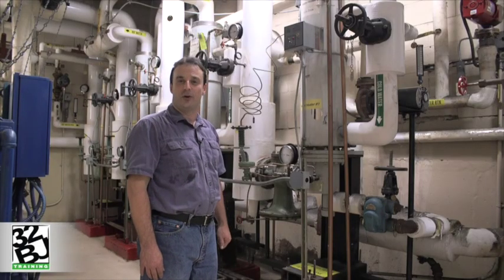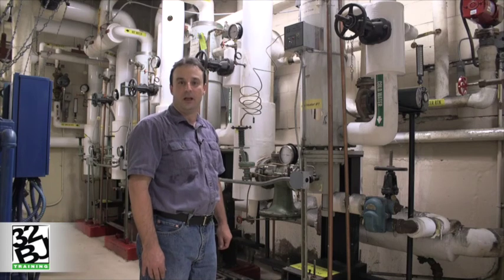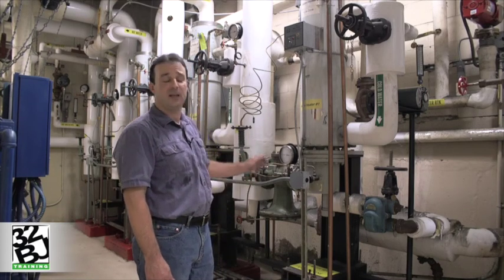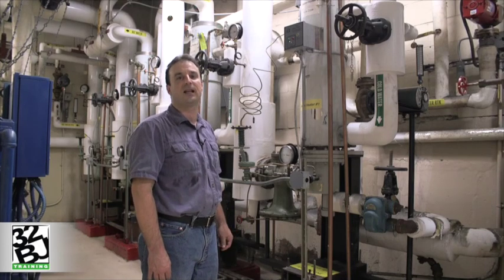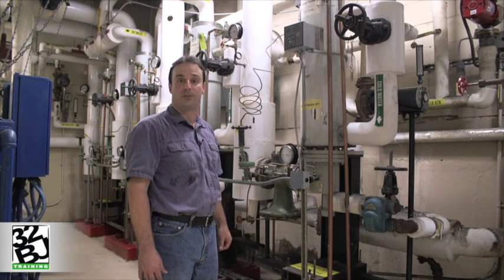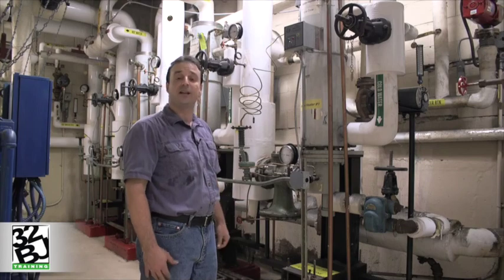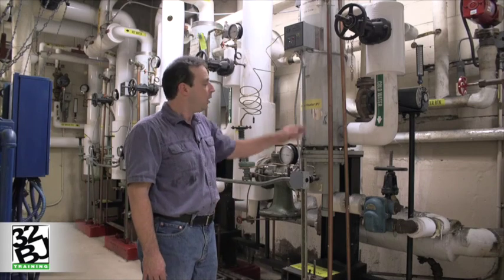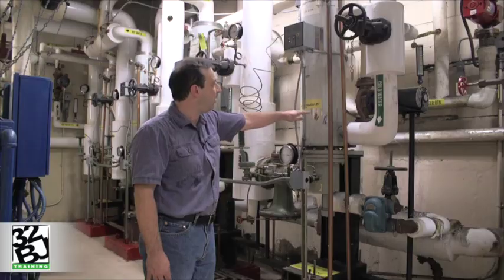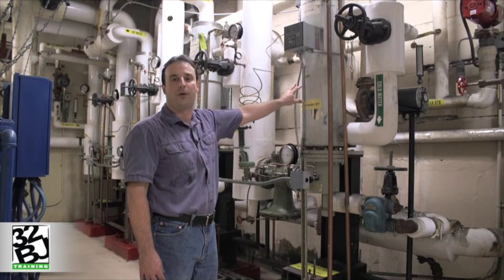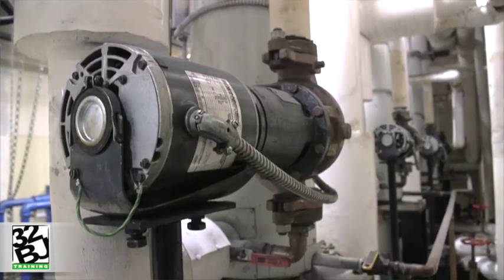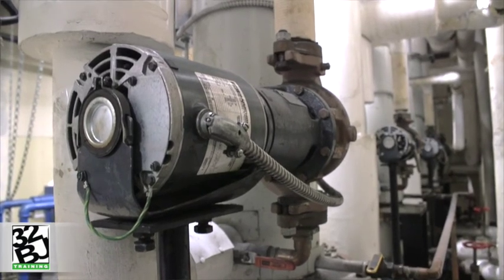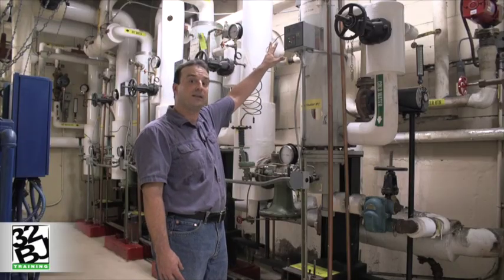This next 30-story multifamily residential building uses a series of semi-instantaneous hot water heaters to keep up with the high domestic hot water demand in a large building. As tenants use domestic hot water, cold water moves into the shell of the semi-instantaneous hot water heater. A small pump continually mixes the water inside the shell in order to give the thermostat up on top an average water temperature.